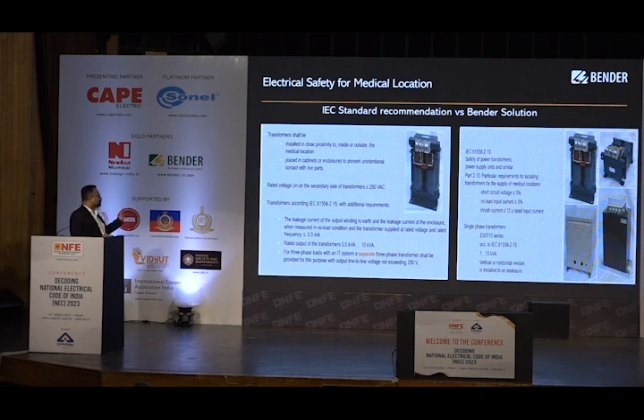So how to do that? You have to put in an isolation transformer, a special type of isolation transformer that IEC is saying. This is the transformer standard we know, the 61558 standard, and all its parameters have to be followed. But 7-710 of 60364 has given some special conditions. The transformer should be in the range of 0.5 to 10 kVA, the leakage current in no load condition should be less than 0.5 milliampere, and it cannot be more than 10 kVA rating.